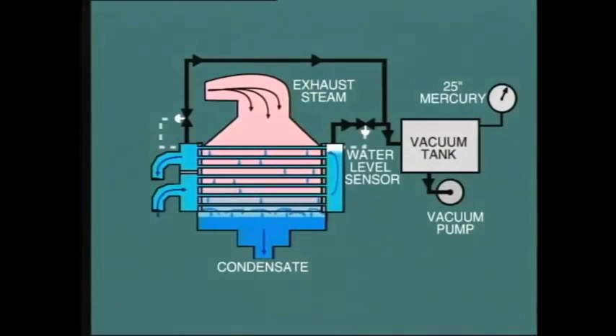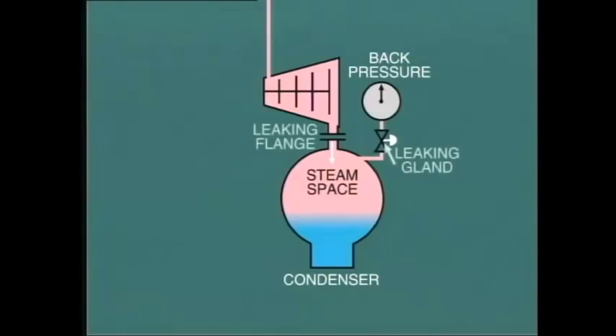A water level sensor in the water box operates a control valve on the siphon connection. When the level falls below a set level, the valve opens and air is drawn out, allowing the water level to rise. When the level rises to fill the water box, the control valve closes. The problem of air accumulation may also occur inside the steam space of the condenser. Remember that this area operates under a negative pressure, a vacuum. Therefore, any leakage by valves, piping, or flanges will allow air to leak into the steam space of the condenser instead of steam leaking out.